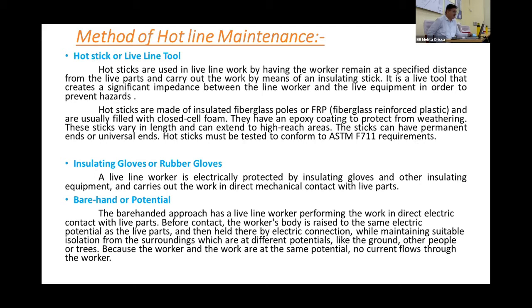Sometimes the bare hand or potential method is also used. Here, the potential of the worker's body is raised to the voltage level of the equipment, say 132 kV or 220 kV. Proper precaution has to be taken, and his body should have the necessary distance clearance from any grounded part or object of the network or equipment, so no current flows through the worker, and the worker and the work are at the same potential. This gives a lot of flexibility for a worker to attend the job very well, because it feels as if he is working on dead equipment.